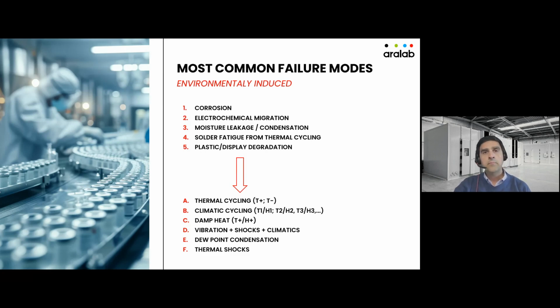Okay, so it's common, for example, when we are testing not for a component, but rather an assembly, that there's a measuring of temperature inside that assembly to see how well it's behaving versus outside conditions. So this is temperature only.